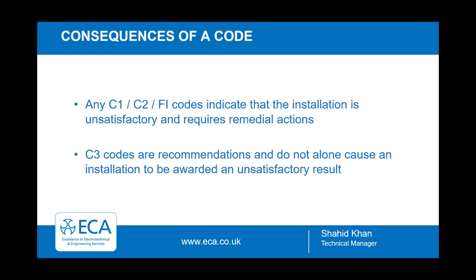In other words, if I was to do a periodic of, say, a factory, and I found 1 C1, 2 C2s and 12 C3s, the installation will be unsatisfactory. However, if I only found 12 C3s, the installation will be satisfactory and fit for continued use. It's only C1, C2 and FI that fail an installation.